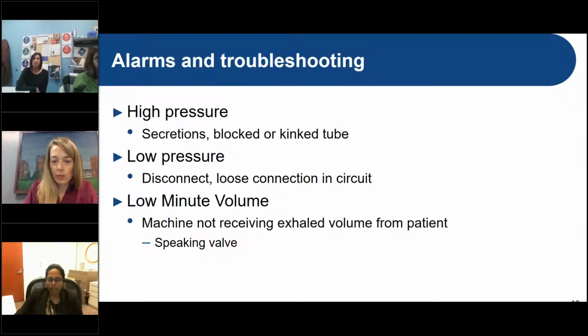Low pressure, or something is missing, could be a disconnection of the ventilator circuitry from the tracheostomy tube itself, or a loose connection in the circuitry. When we're using artificial humidification, the circuit will have temperature probes and wires within it that could pop off. So after thoroughly inspecting the airway, we work our way down the tubing to make sure all of our connections and tubing are tight. Lastly, we have our low minute ventilation alarm.